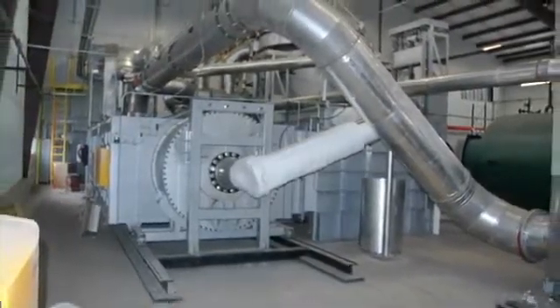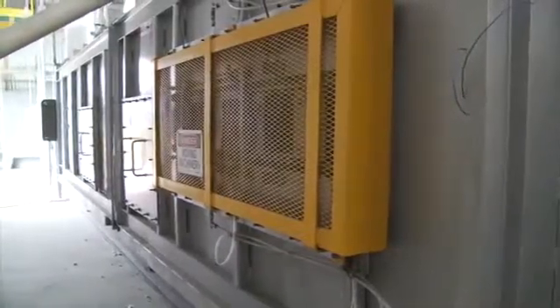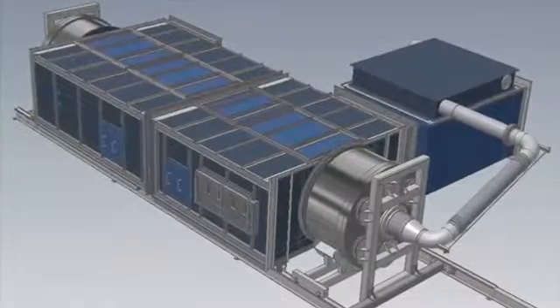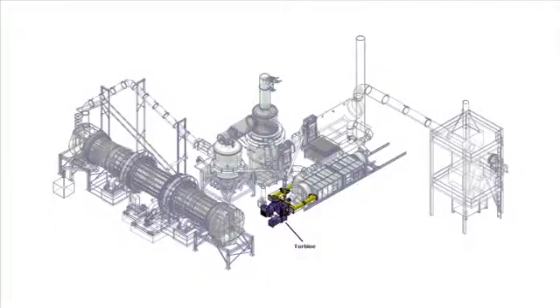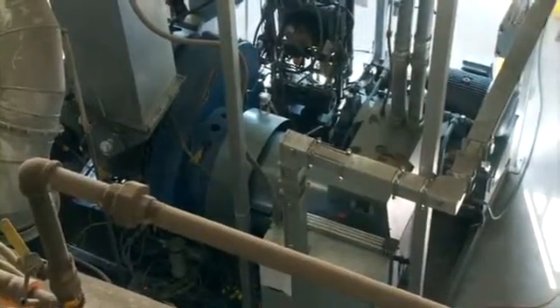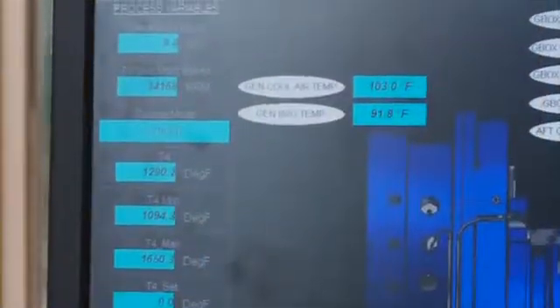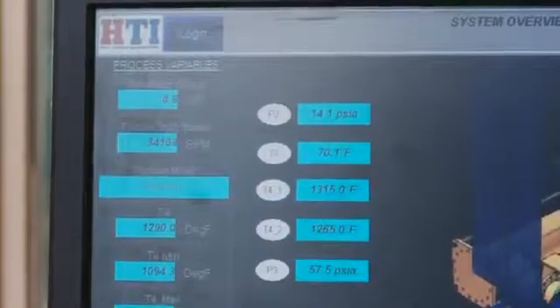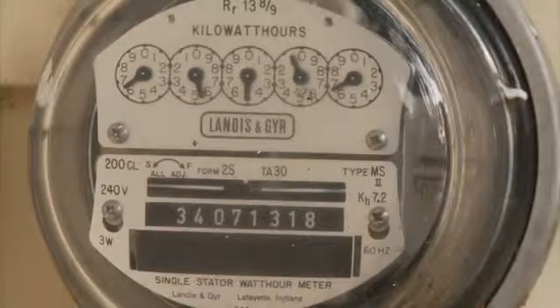The turbine air is compressed and forced through the exchangers where it picks up energy. From the metal exchangers, the air is then forced through the ceramic heat exchangers to pick up high-grade energy to spin the turbine. As the heat energy from hot, clean air enters the air turbine, the turbine is allowed to engage. The turbine spins the generator, creating electricity, which is transferred to a commercial electrical grid.